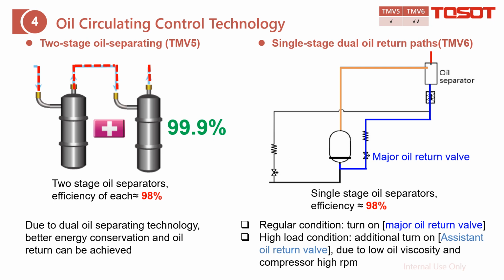At that time, we create another one, which is this assistant oil return valve, to ensure enough oil can flow back to the compressor for lubrication. And just for your information, if the outer ambient is low, the compressor is always at high frequency. At that time, it always requires more oil for lubrication.